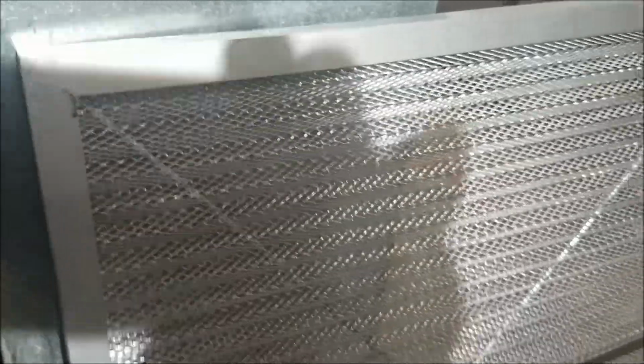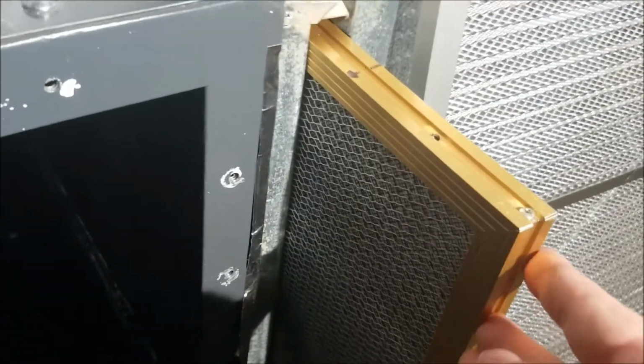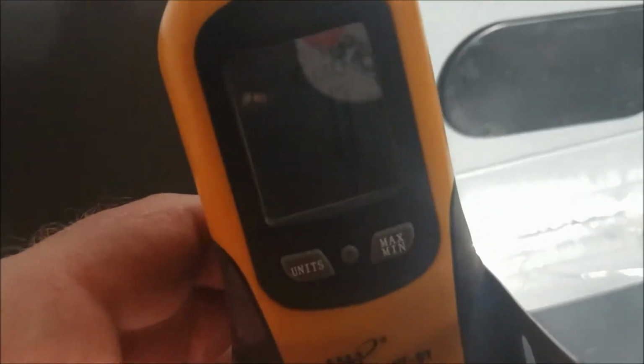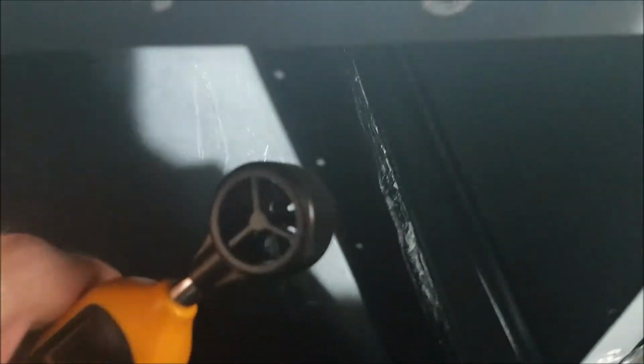I'm going to test the CFM of the system. I've removed the filter that's in here. It's basically this filter here. I'm not using that. I already got one in there that's like a MERV, I don't know, 8 or 9 here. So no need to have 2 filters. And I'm going to use the velocity meter here, anemometer, so it's set at velocity and feet per minute. So that'll determine the linear feet per minute, and then once I get the linear feet per minute, then I can figure out what the cubic feet per minute is. So that'll be the next thing here. So I got a little makeshift stand so it doesn't blow over when I start sucking air through the system.